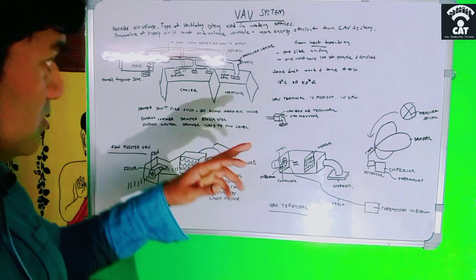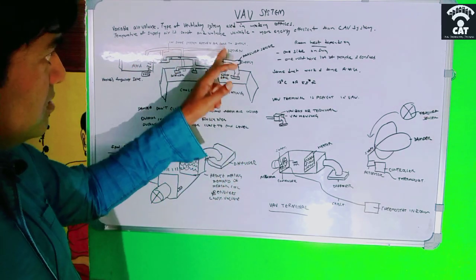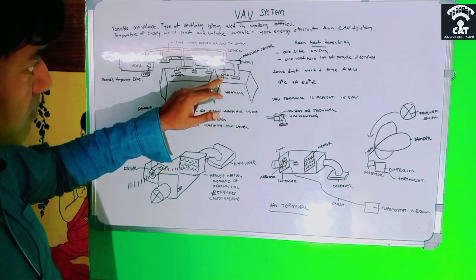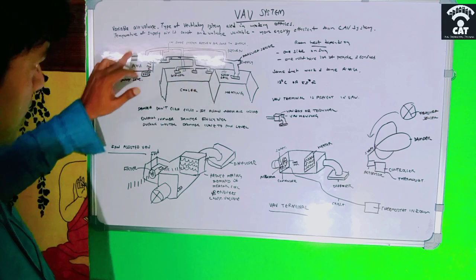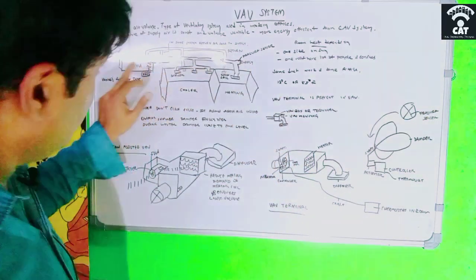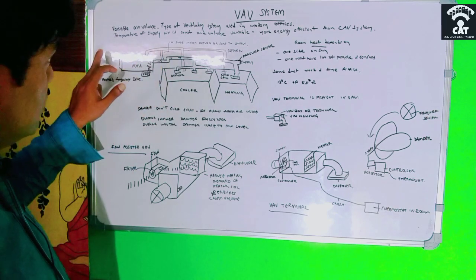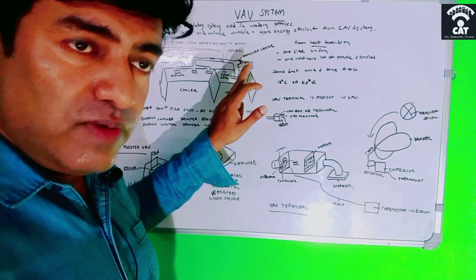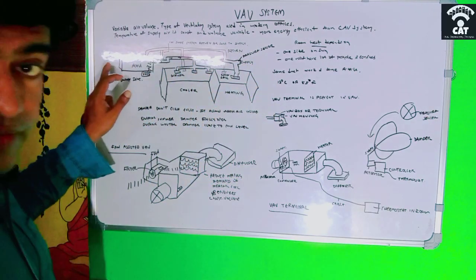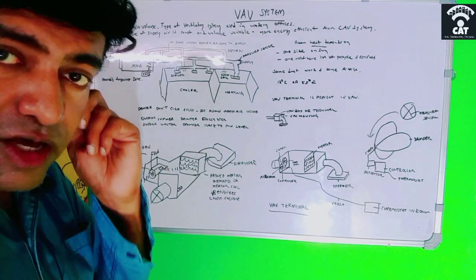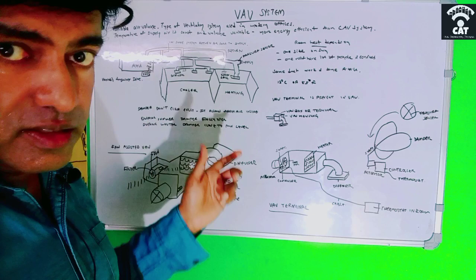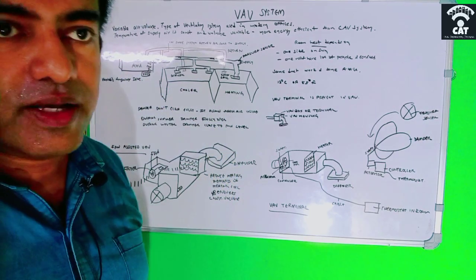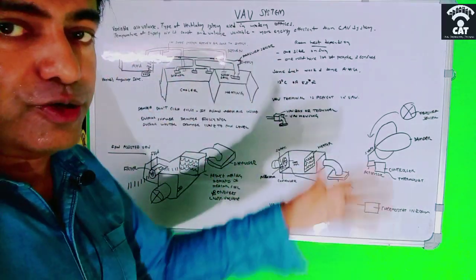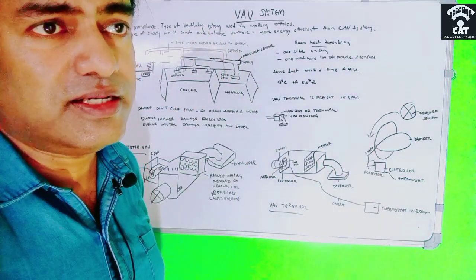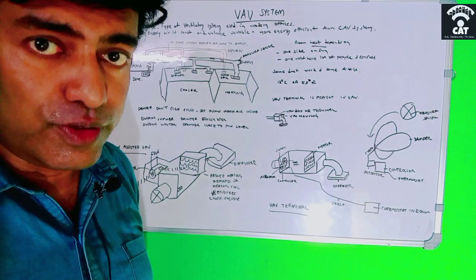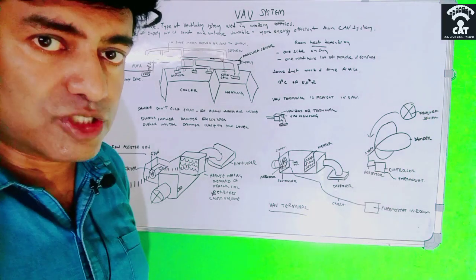So that is the system. Before that, I want to tell one more thing. I told you this is the supply duct and this is the return duct. The return air will go through this return grill, and it will go like this. In some systems, before the AHU, which I didn't show here, this return grill will have a connection with the duct which takes air from outside into the AHU. There's a connection between that duct and the return duct, so that whatever air is inside the room will be recirculated into the AHU. That is one system, but it depends upon whether the local regulation will allow it or not. Usually we are not doing that, but there is a system like that too.